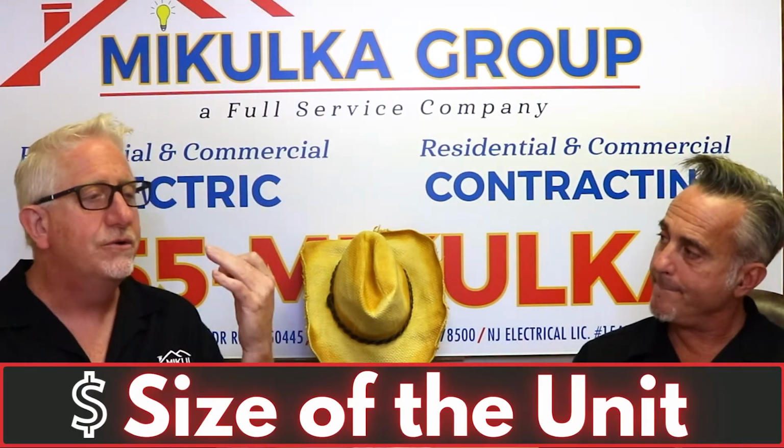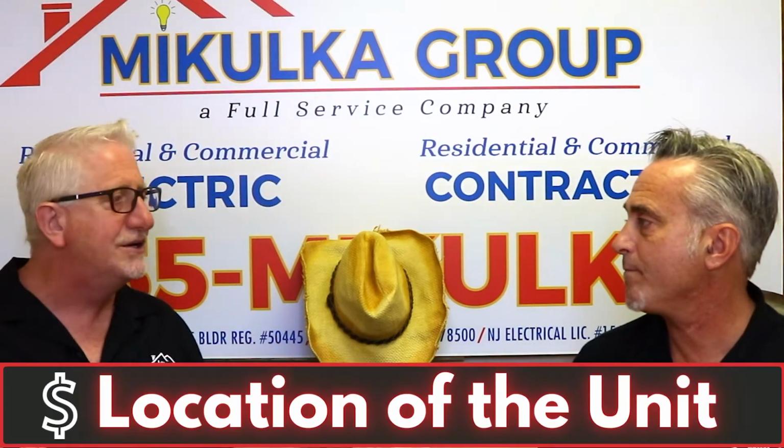How big is it? So 14 kilowatt, 18 kilowatt, 22 kilowatt, 24 kilowatt. And basically what those numbers are is the amount of available electricity. So if you have a typical 4-bedroom, 2-bath, with 1 zone of AC and some other basic electric appliances, an 18 or a 22 is going to be fine. And you could go online and just get a retail price for that. But what also drives the cost, besides the size of the unit, is where it's going to go.